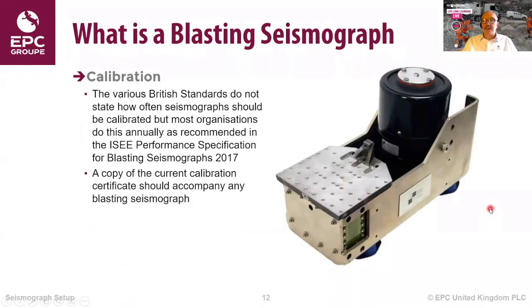Seismographs should generally also be calibrated. There's no standard for how often this should be done, but most people apply common sense and will calibrate their seismographs every 12 months. And that's what's recommended by the ISEE. And the copy of the calibration certificate should accompany any seismograph. In the calibration process, it will be put on a shaking table. In this case, on the top here for vertical vibration, that could be rotated round and the seismograph placed on here for horizontal calibration. The calibration process will check that vibration recording against a standard that can be traceable back to a national standard.